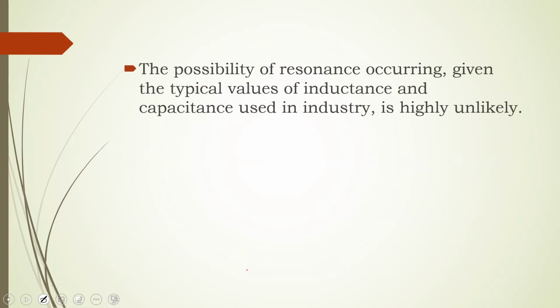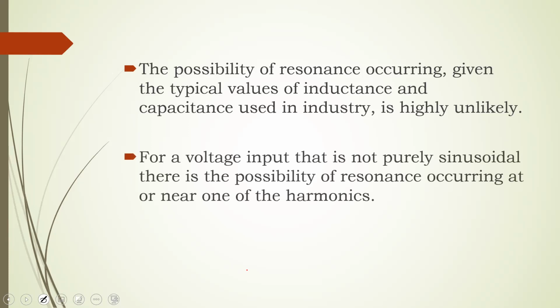Now, as I mentioned just now, there is the possibility of resonance occurring. I shouldn't put it that way. The resonance occurring is not very likely, right? In terms of an industrial setting, okay? And that is at the power frequency. Good? However, when you have a non-sinusoidal, because you are now exposing those same reactive elements to a myriad of frequencies, that possibility now increases. So let me say that again.